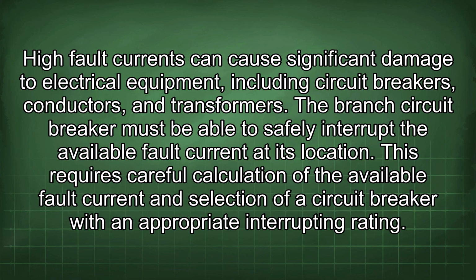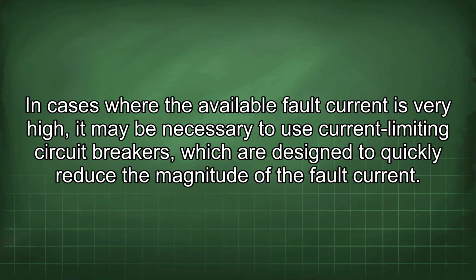The branch circuit breaker must be able to safely interrupt the available fault current at its location. This requires careful calculation of the available fault current and selection of a circuit breaker with an appropriate interrupting rating. In cases where the available fault current is very high, it may be necessary to use current-limiting circuit breakers, which are designed to quickly reduce the magnitude of the fault current.